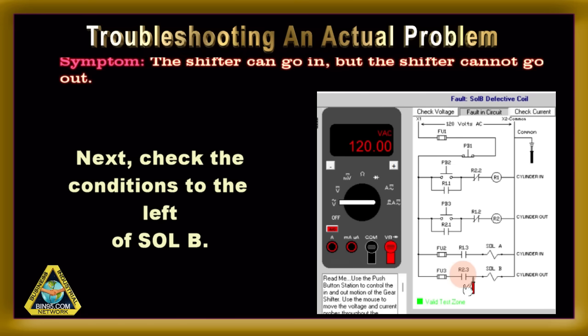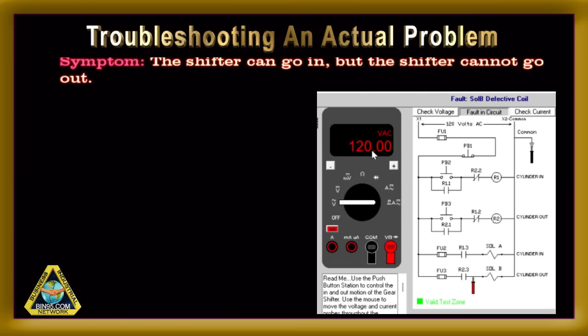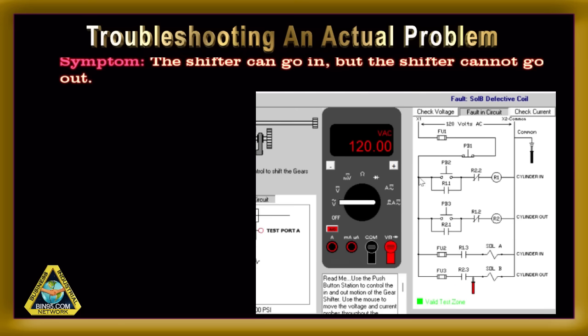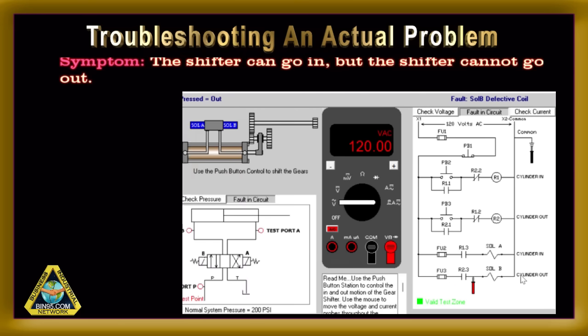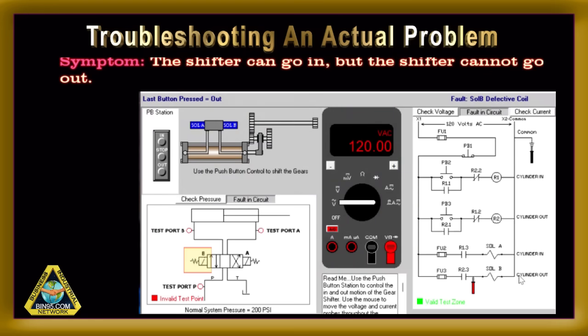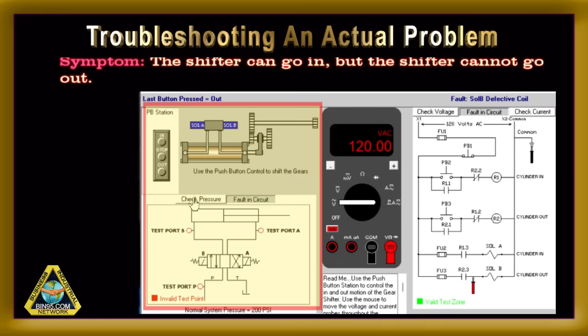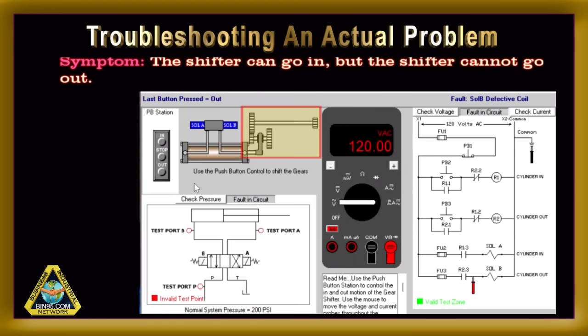We check that condition, asking: is voltage getting through contact R2.3 to the cylinder out solenoid coil? As we see, the answer is yes. This means the problem is either the coil is burnt out, open, or some other issue outside the control panel. It could be mechanically jammed, the air is off to the cylinder, etc.